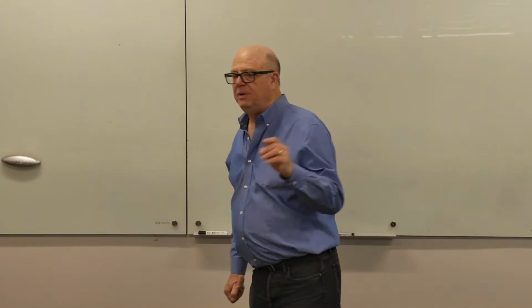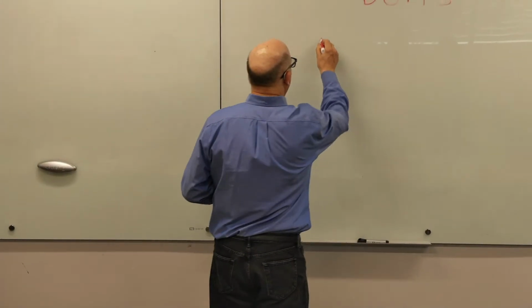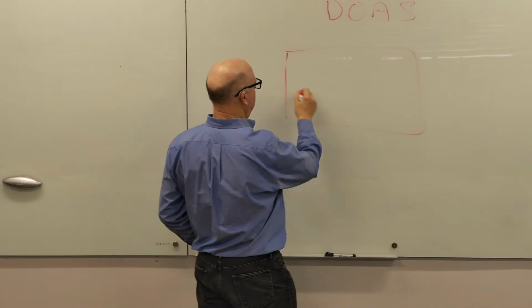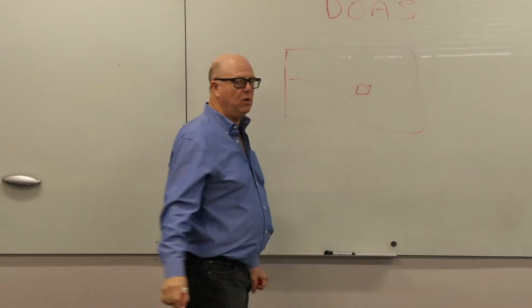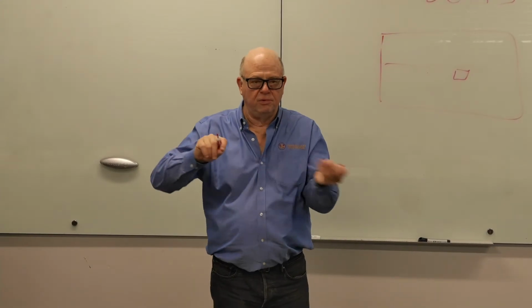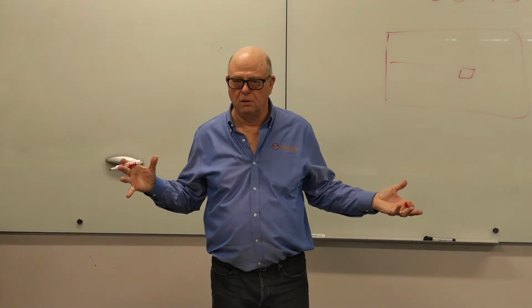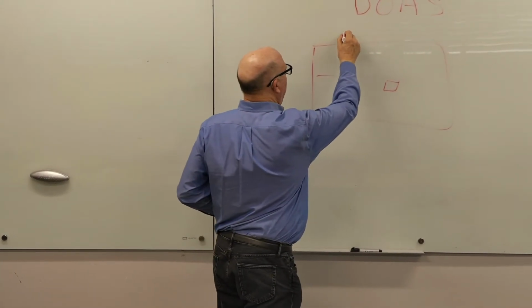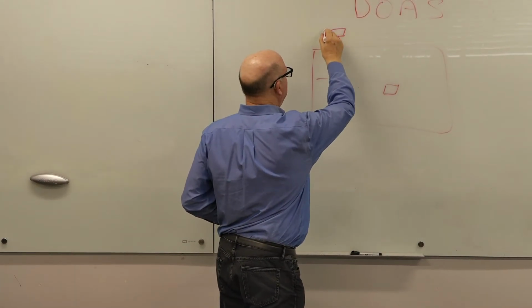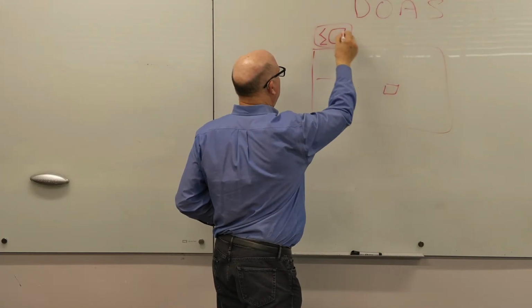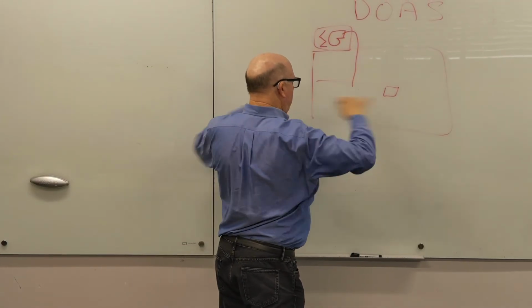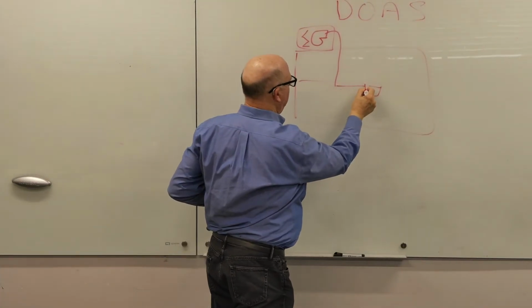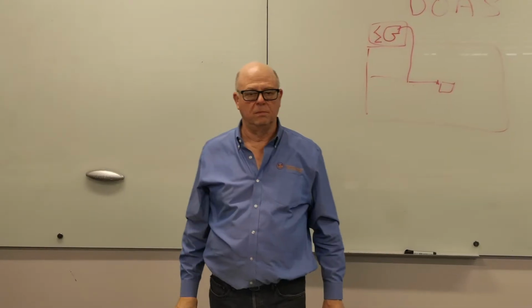Code requirements. VRF. All of those answers are right. Let me tell you a little bit about VRF before we move on. Back in the day, you would have a building, and it would have chilled water fan coil units in it. And if it was 4-pipe, it'd have hot water fan coils as well. And you'd have some supply fan up on the roof. Wouldn't have cooling, wouldn't have heating, it'd have a filter. And it would bring air down, distribute it, and it would drop some air off right behind this fan coil.